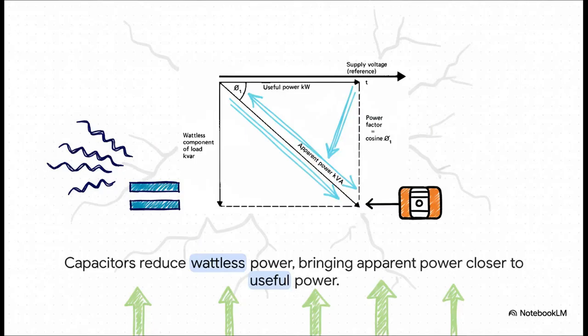You can see that in this classic power triangle. The whole goal is to shrink the apparent power side of the triangle so it gets closer to the useful power side. A lot of electrical equipment, especially big motors, creates this thing called reactive power. PFC uses capacitors to cancel out that wasteful part, which means the utility doesn't have to pump out as much total power to get the same amount of real work done.